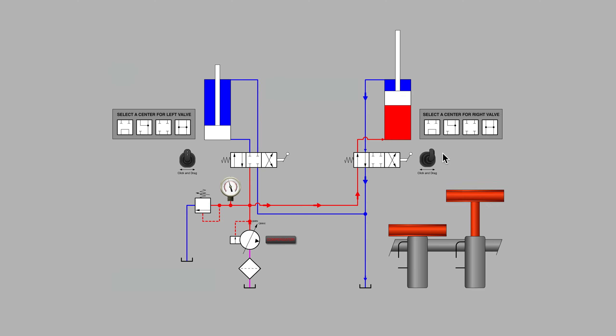So that's the advantage of putting a pressure compensated pump to work. And without pumping any fluid over the relief valve, the pump does allow for a fair amount of energy to be saved. Pressure is being maintained, but at a very, very minimal flow rate only the flow rate needed to make up for internal leakage inside the pressure compensated pump or any other internal leakages that may exist in the hydraulic circuit. So that is a good way to save energy and avoid building heat.